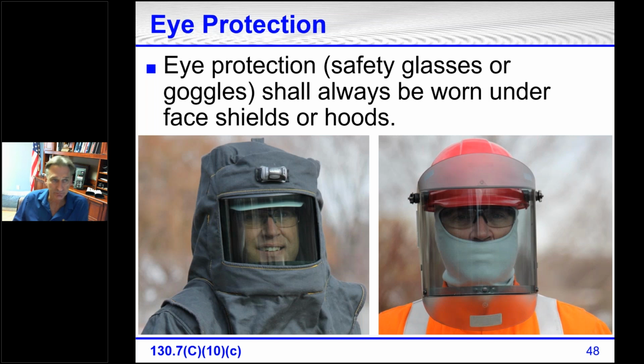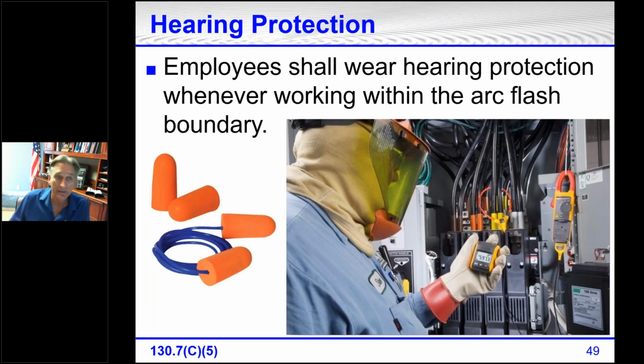Hearing protection. Employees have to wear hearing protection whenever working within the arc flash boundary. If the arc flash boundary is 3 inches, no, you don't have to wear hearing protection. Well, maybe if you're in a plant that requires hearing protection, then yes, you do, but not because of 70E, but because of your own safety rules.